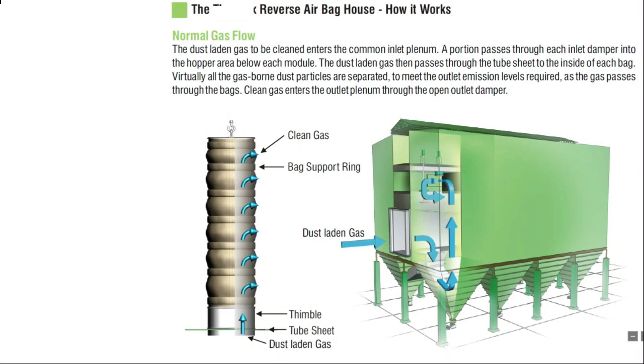How it works: The dust-laden gas to be cleaned enters the common inlet plenum. A portion passes through each inlet damper into the hopper area below each module. The dust-laden gas then passes through the tube sheets to the inside of each bag. Virtually all dust particles are separated to meet the required outlet emission levels. As clean gas passes through the bags, it enters the outlet plenum through the open outlet damper. The blue color arrows in the picture indicate the flow of the gas.